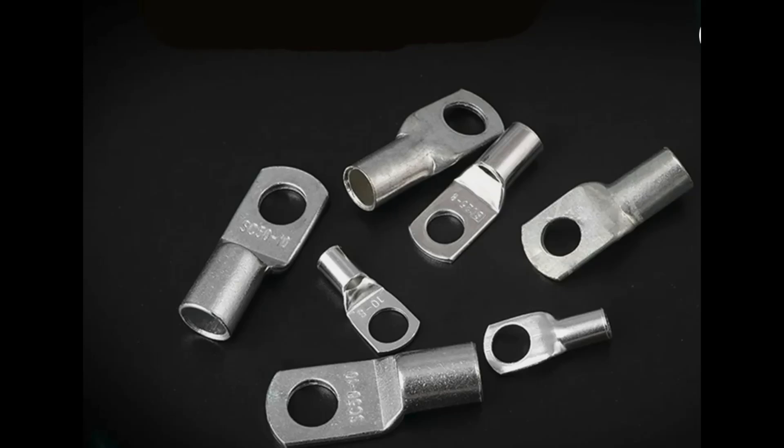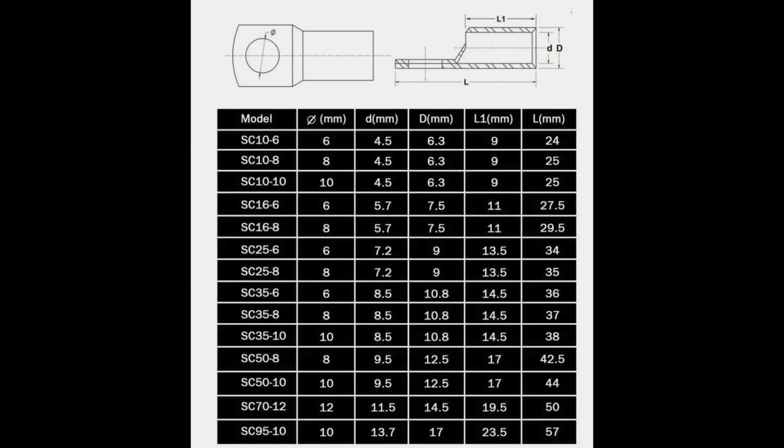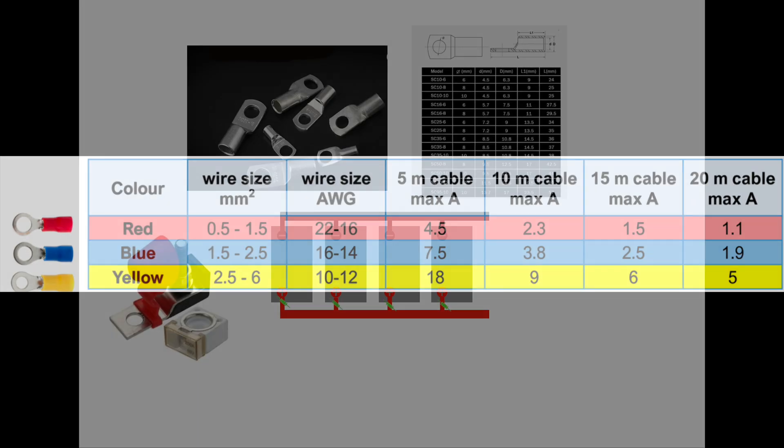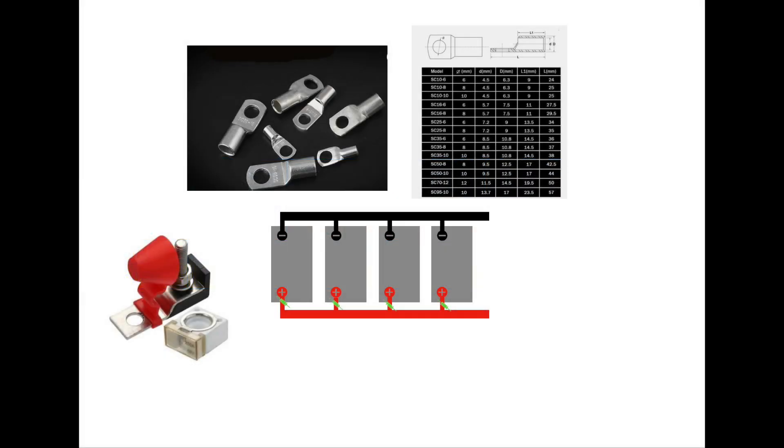Cable crimps or lugs are similarly sized either in AWG or in cross-sectional area. In Europe we tend to use cross-sectional area, but there are some crimps and lugs which come into the country using AWG. The connection hole in the lug or crimp is also sized either in imperial or in millimetres diameter. This information is readily available on the internet. Make sure you know exactly the size of cable and lug that you need and how many amps it's going to carry. Whichever size cable, fuse, lug, breaker or crimp you're going to use, I must emphasize you need to buy quality products. If they feel lightweight or cheap, they are, and it could cause a fire.